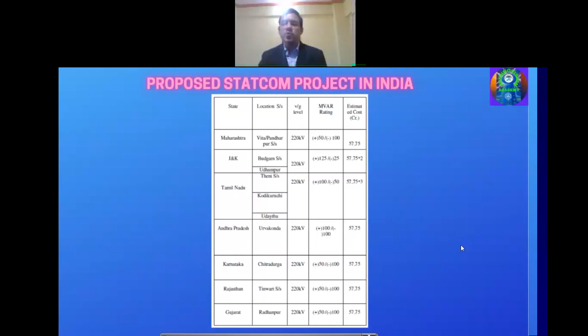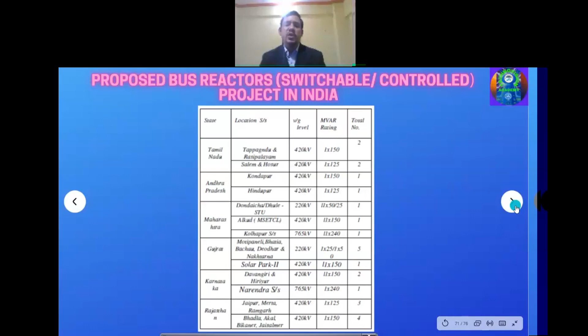So these are the switchable controls. These are the bus reactors. Especially, these are not particularly FACTS devices, but these are mechanically switched. Just by switching the breaker on and off, you can take these reactors into service. Manual operation is there to maintain the voltage profile in the system. These bus reactors are generally used at 765 kV, 220 kV and 400 kV levels.